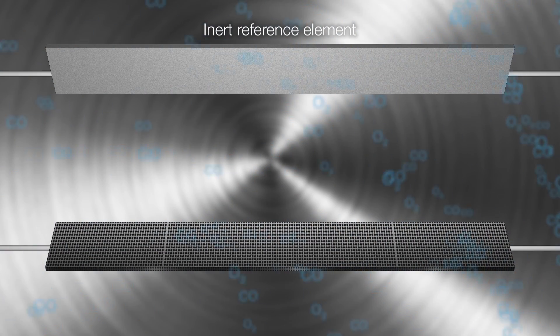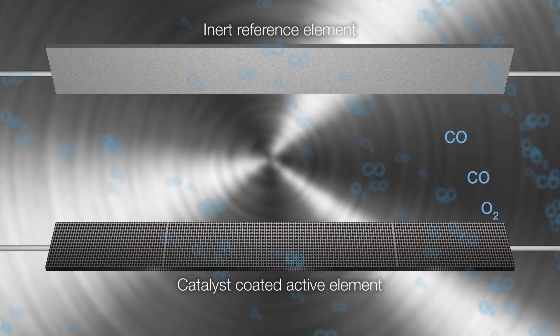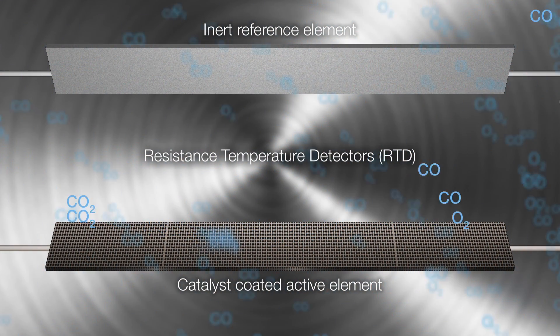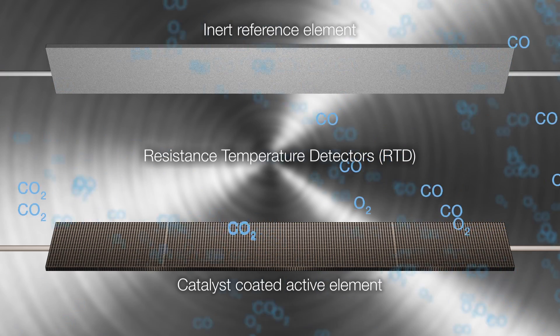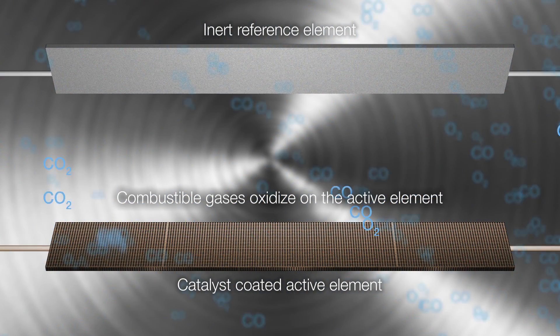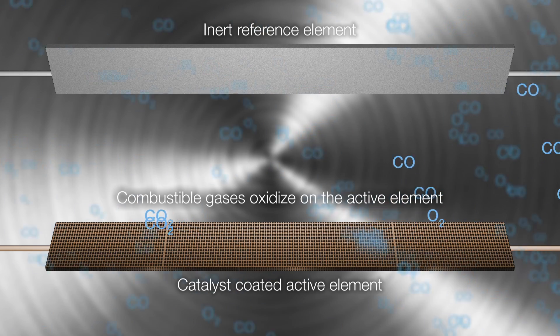The CO sensor consists of an inert-coated reference element and a catalyst-coated active element. Both elements are resistance temperature detectors, or RTD. As the sample gases flow by the sensor, the combustible gases oxidize on the surface of the active element.